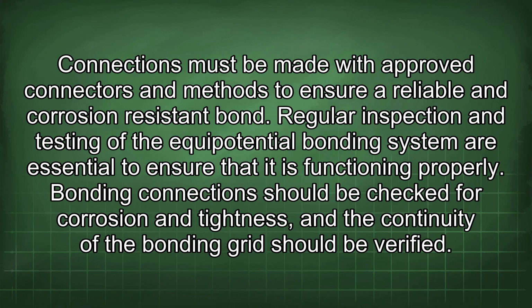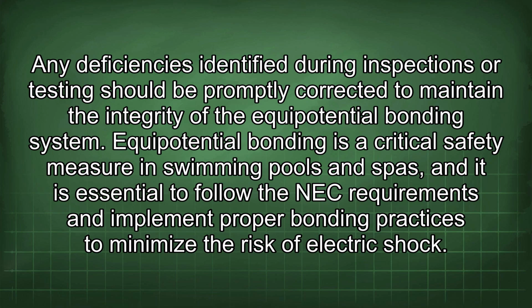Regular inspection and testing of the equipotential bonding system are essential to ensure that it is functioning properly. Bonding connections should be checked for corrosion and tightness, and the continuity of the bonding grid should be verified. Any deficiencies identified during inspections or testing should be promptly corrected to maintain the integrity of the equipotential bonding system. Equipotential bonding is a critical safety measure in swimming pools and spas, and it is essential to follow the NEC requirements and implement proper bonding practices to minimize the risk of electric shock.